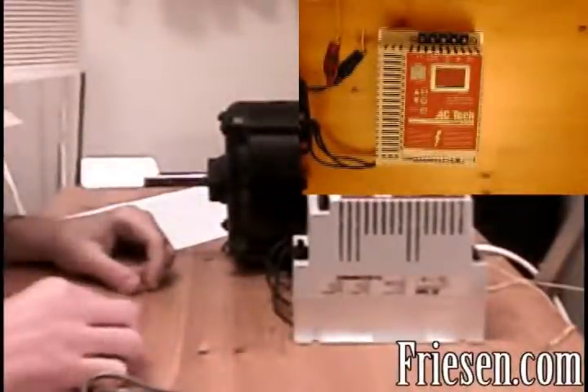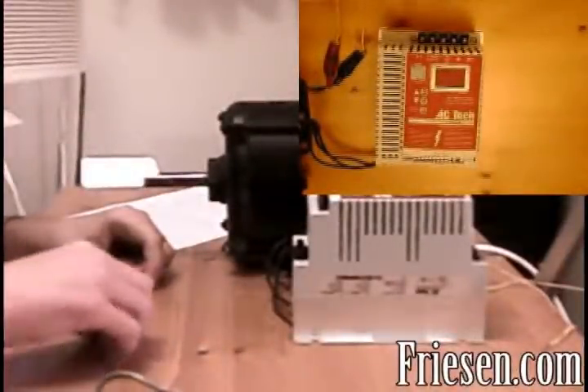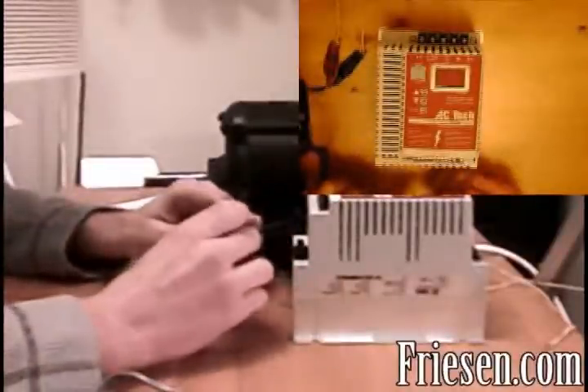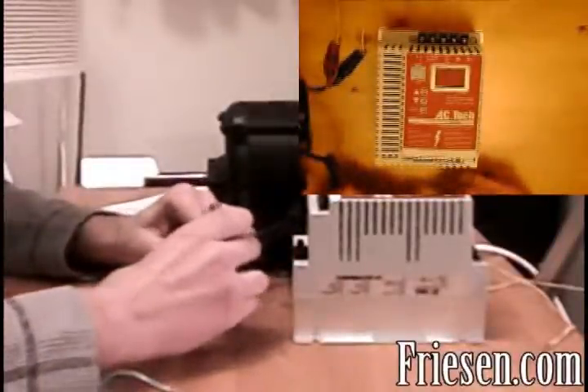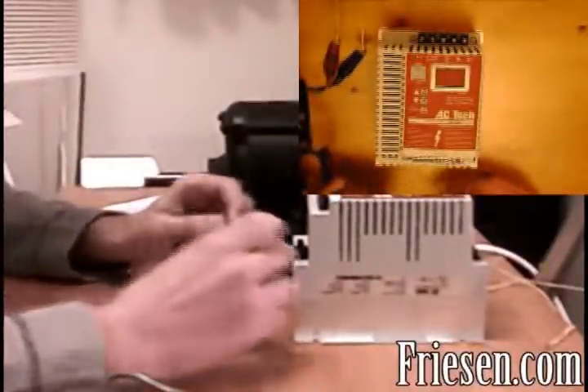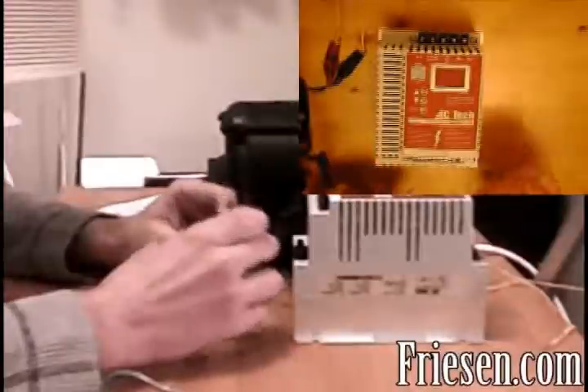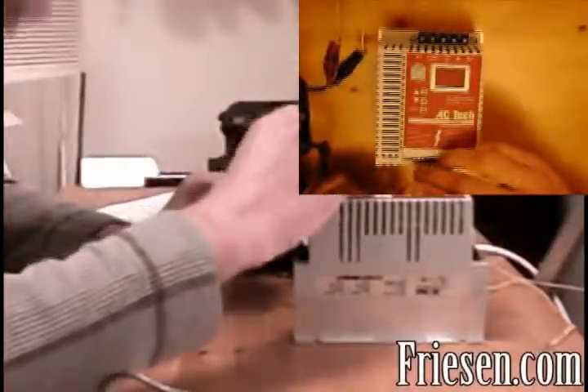The first step will be to connect all of our components to the variable speed drive. We'll start by connecting the three motor leads to the bottom part of the drive, to the connectors labeled U, V, and W.